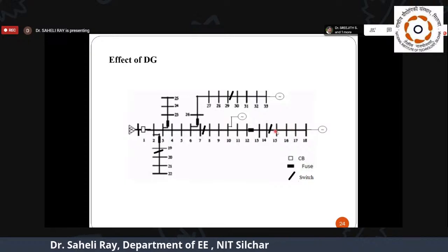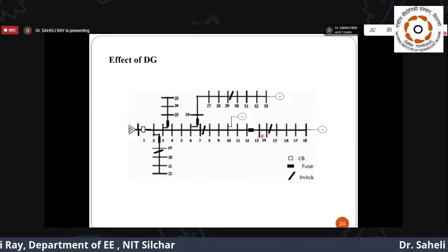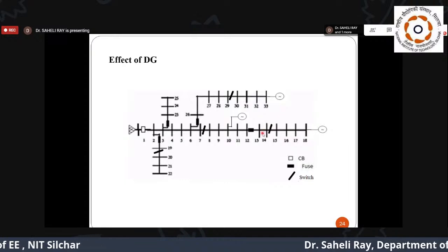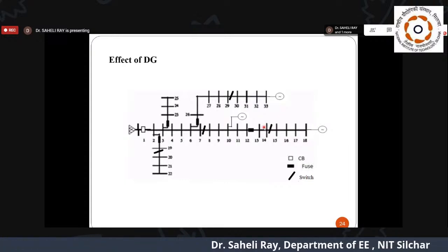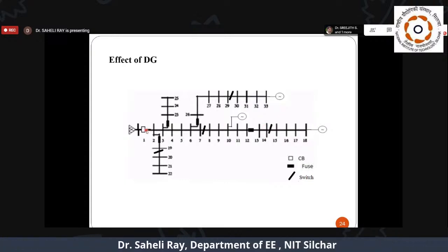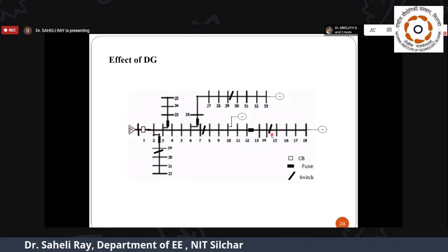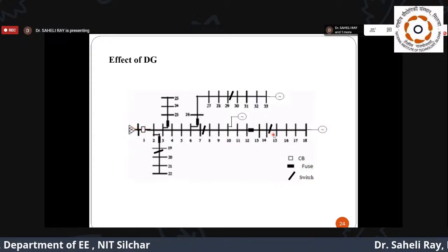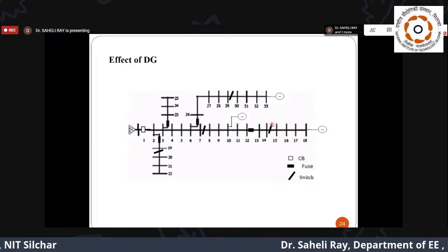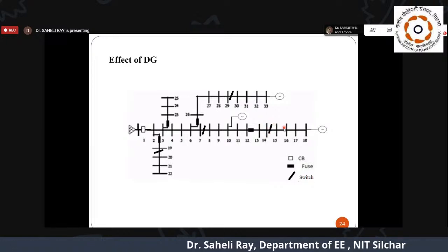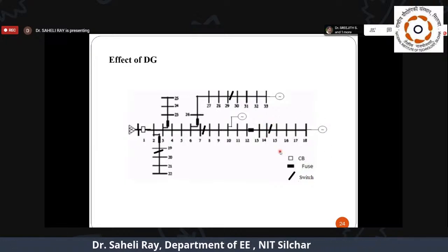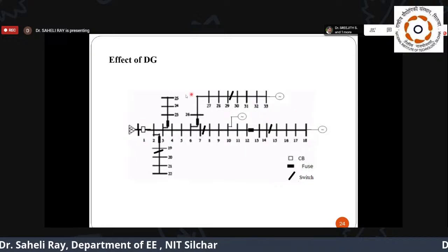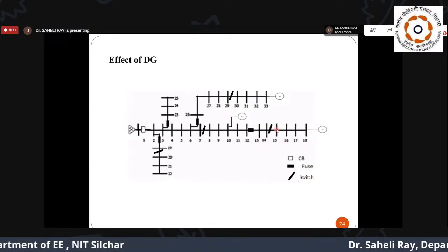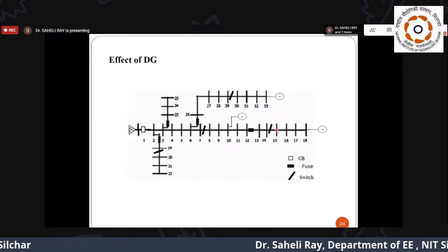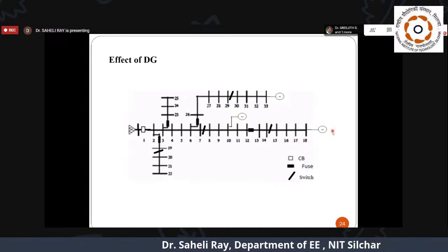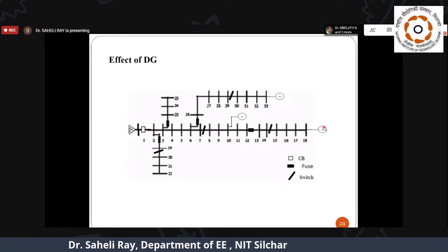In this situation, if a fault occurs in between 13 and 14, obviously initially the breaker will operate and trip, and the interruption will be there. But after that, by operating this switch, we can isolate this portion, load points 15, 16, 17, 18, from the remaining portion, and this may act as an isolated set of load points supplied by the distributed generator present.